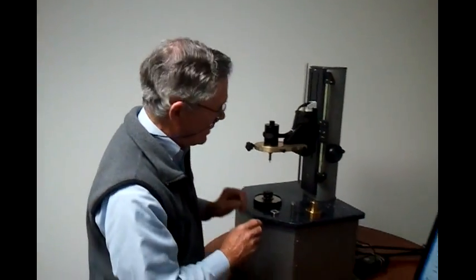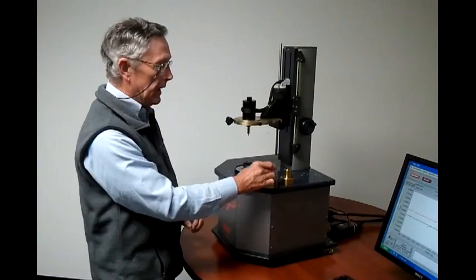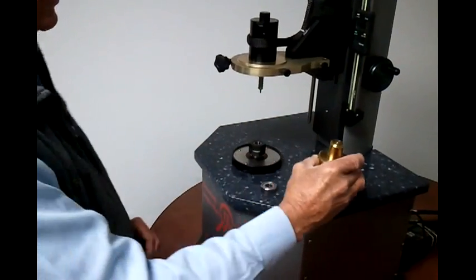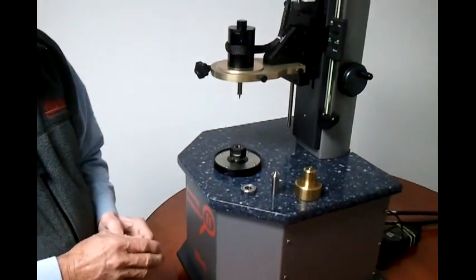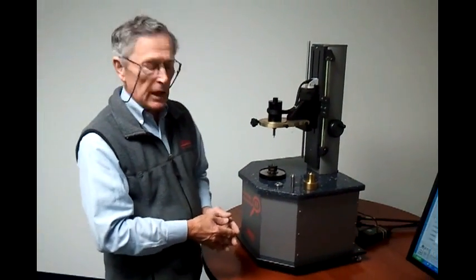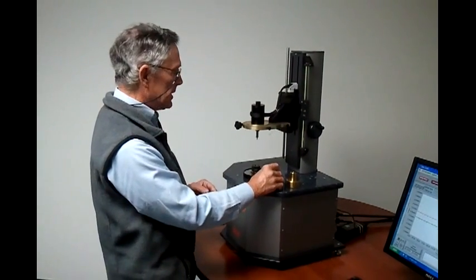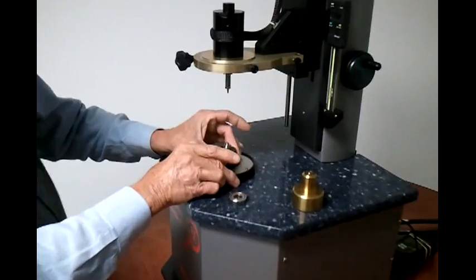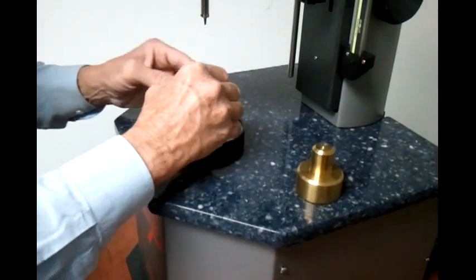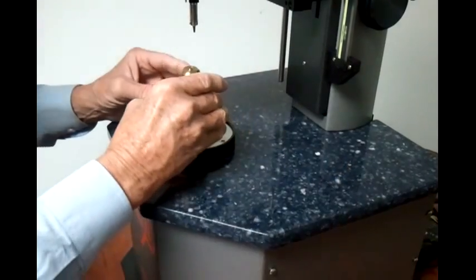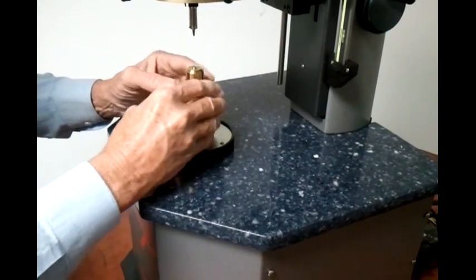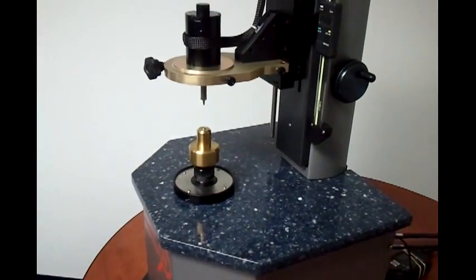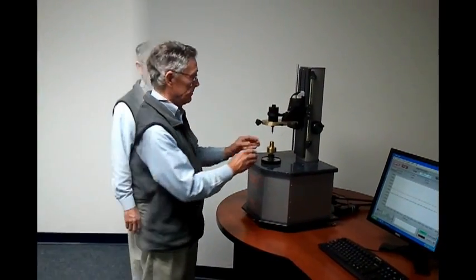Put the cover back on and you're ready to test. The tooling has two elements: an ID tool and an OD tool. The OD tool provides the load that is described in the specifications. We place the ID tool into the spindle and tighten the nut to hold it in place. We place the bearing we're going to test on the spindle, then we place the load on, at which point the device is ready to perform a test. We will now go on to phase two of the testing process.